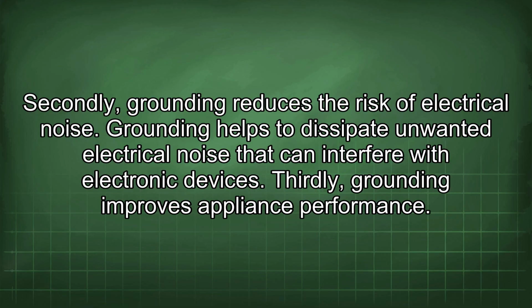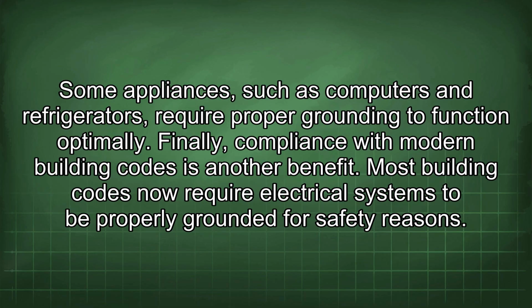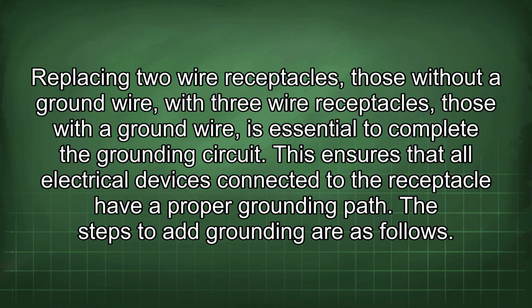Grounding helps to dissipate unwanted electrical noise that can interfere with electronic devices. Thirdly, grounding improves appliance performance. Some appliances, such as computers and refrigerators, require proper grounding to function optimally. Finally, compliance with modern building codes is another benefit. Most building codes now require electrical systems to be properly grounded for safety reasons. Replacing 2-wire receptacles, those without a ground wire, with 3-wire receptacles, those with a ground wire, is essential to complete the grounding circuit. This ensures that all electrical devices connected to the receptacle have a proper grounding path.